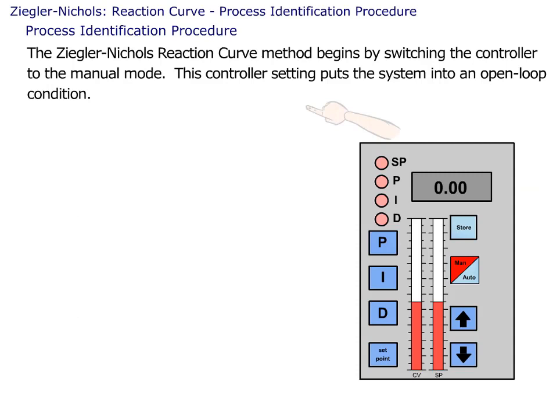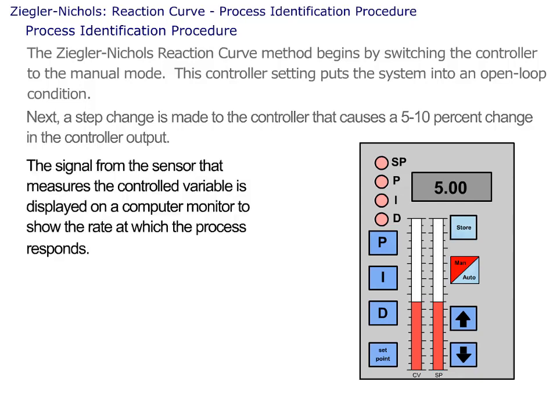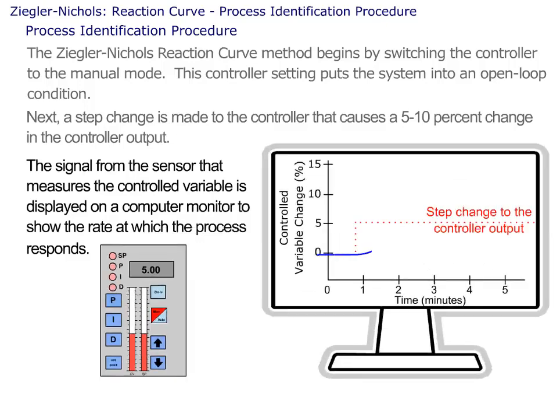The Ziegler-Nichols Reaction Curve method begins by switching the controller to the manual mode. This controller setting puts the system into an open-loop condition. Next, a step change is made to the controller that causes a 5 to 10 percent change in the controller output. The signal from the sensor that measures the controlled variable is displayed on a computer monitor to show the rate at which the process responds.